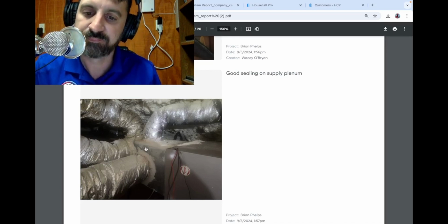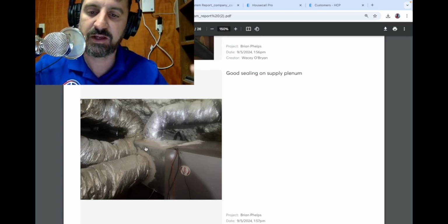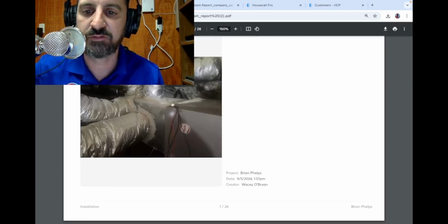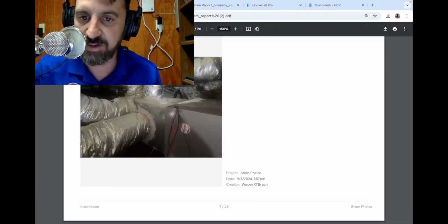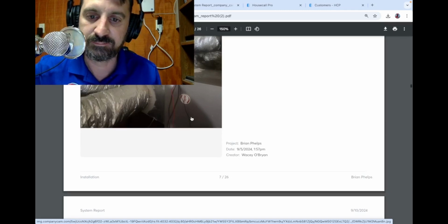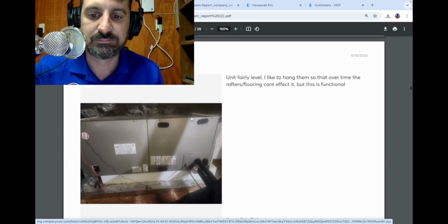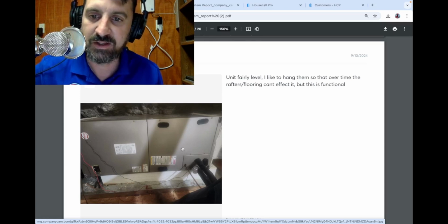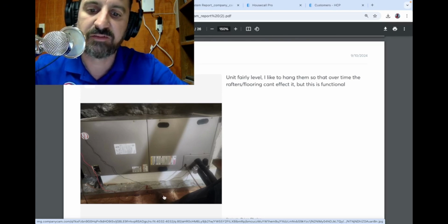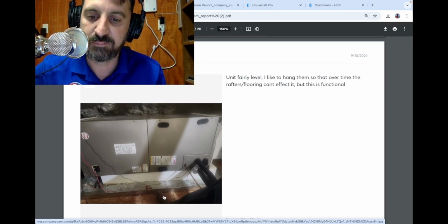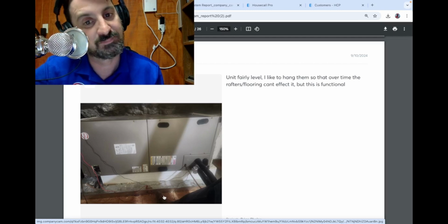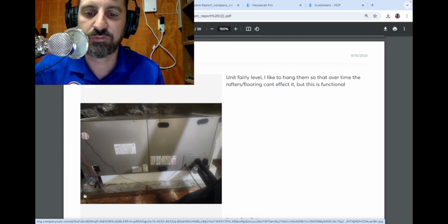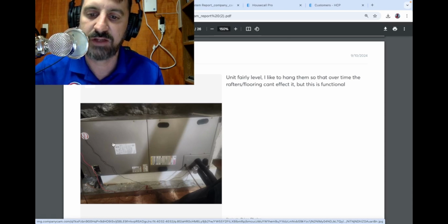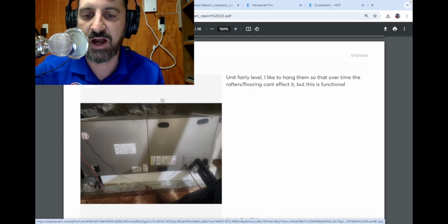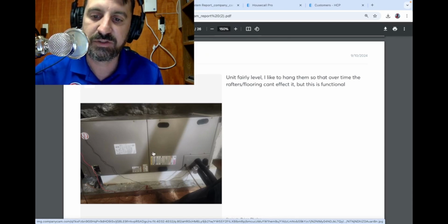If it was my system, I would probably take a CFM hood and make sure that it's putting out the right CFM. But assuming it's putting out the right CFM, this is all sealed good. It's level. I like hanging them rather than setting them on the deck like this. When you set them, it's fine, everything's level. But over years, especially if you get a lot of humidity in your home, like we're going to see here, this wood can shift and settle and end up with one side or the other high or low and cause your drainage to be an issue.